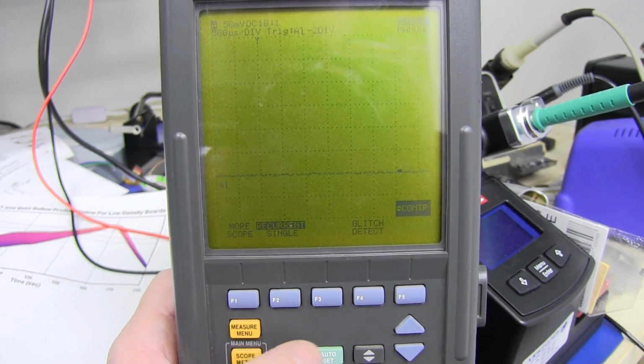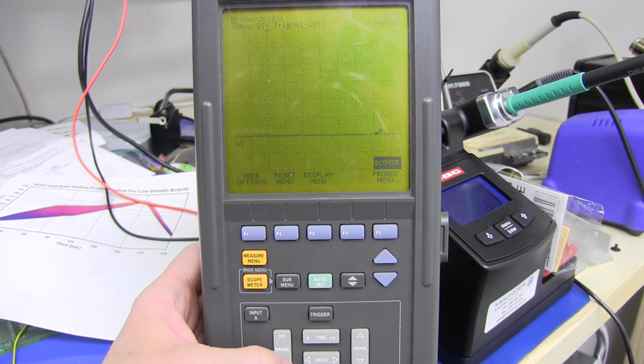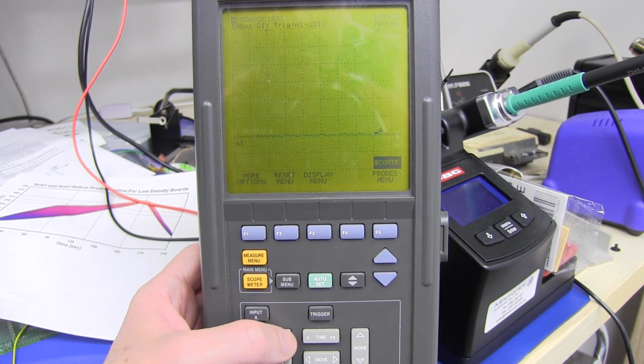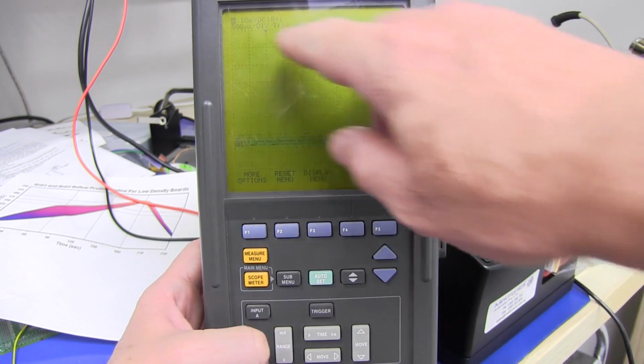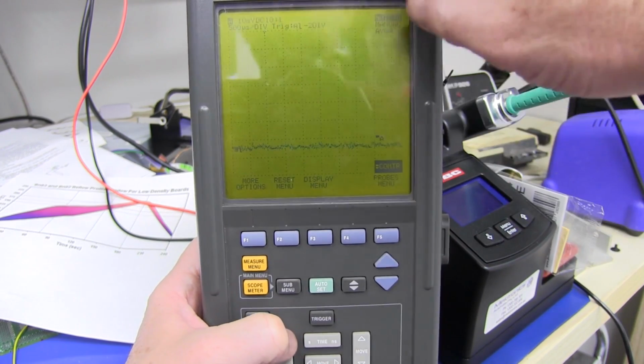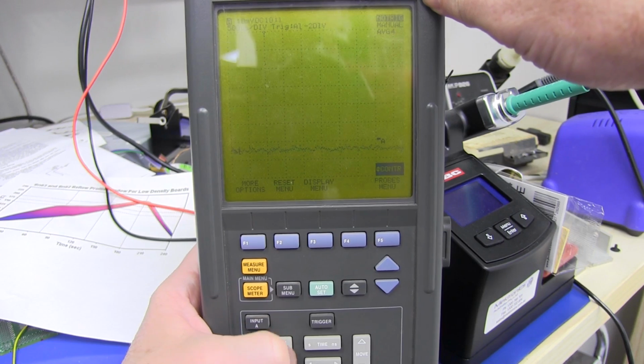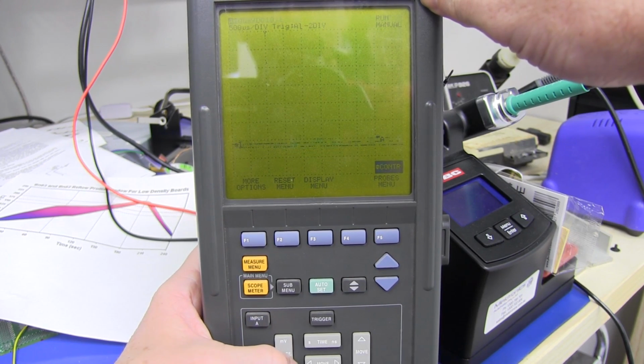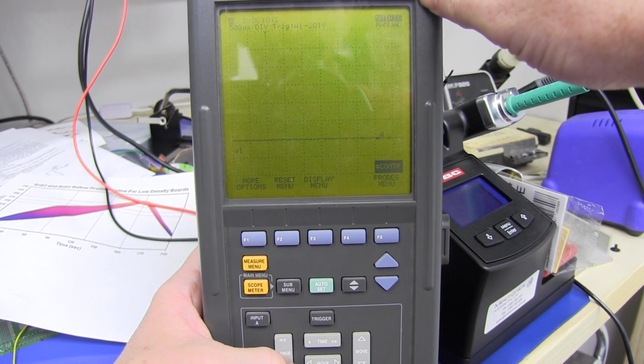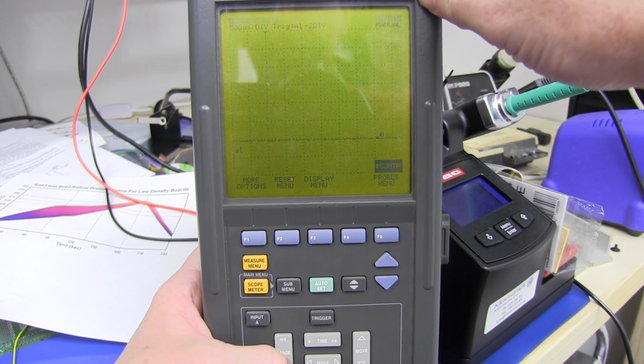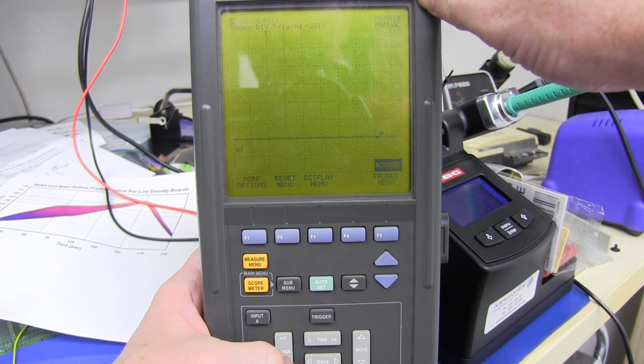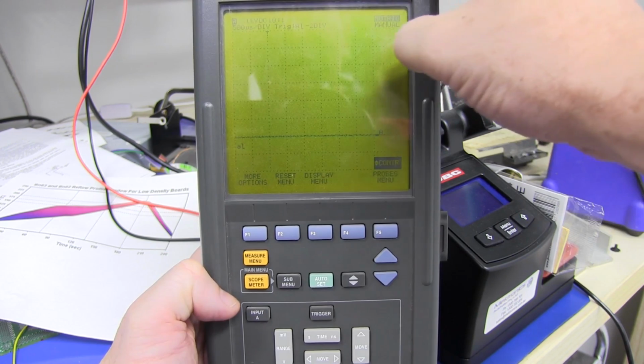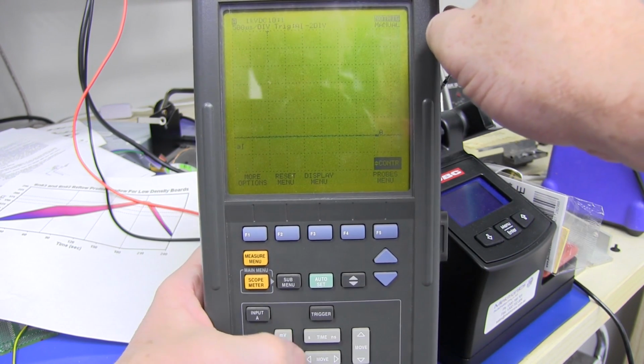It's pretty poor. I mean, we do have dedicated range keys down here, so as you can see, it goes down to 10 millivolts per division with a times 10 probe there, all the way up to 5 volts per division, 10 volts, 20 volts per division, 50 volts, 100 volts per division, 200 volts per division, 500, a kilovolt per division with a 10-to-1 probe.